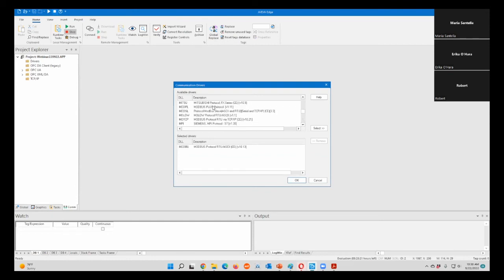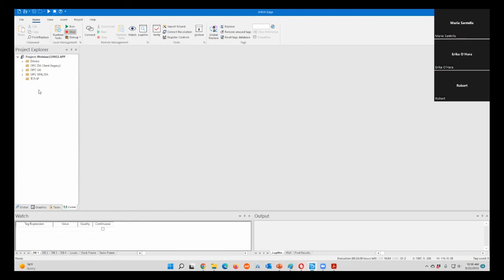Modbus RTU, which is here. Notice the protocol pops up down here, and we will also use Modbus TCP for this application. So we're using both drivers here. They both show up down there. Then we click OK, and then we can expand this tab, and we see both drivers. The first one I'm going to do is Modbus RTU.